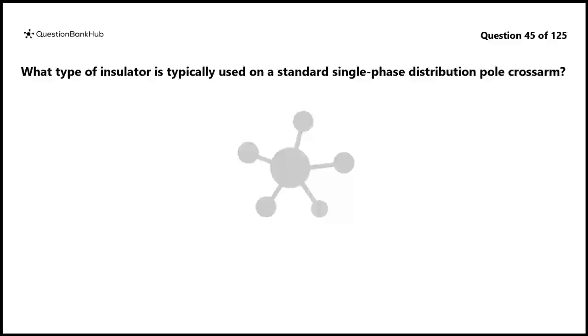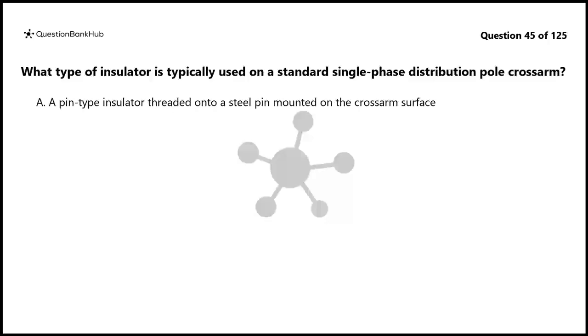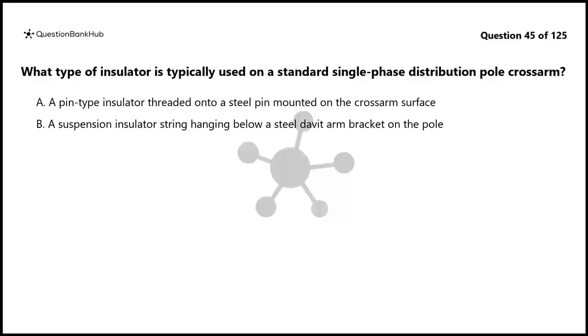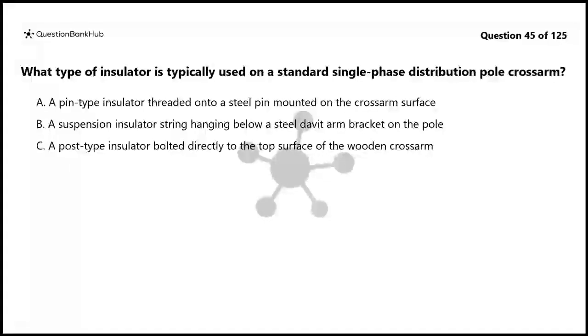Question 45. What type of insulator is typically used on a standard single-phase distribution pole crossarm? A. A pin-type insulator threaded onto a steel pin mounted on the crossarm surface. B. A suspension insulator string hanging below a steel davit arm bracket on the pole. C. A post-type insulator bolted directly to the top surface of the wooden crossarm. D. A strain insulator connected in series with the conductor at each dead-end point.